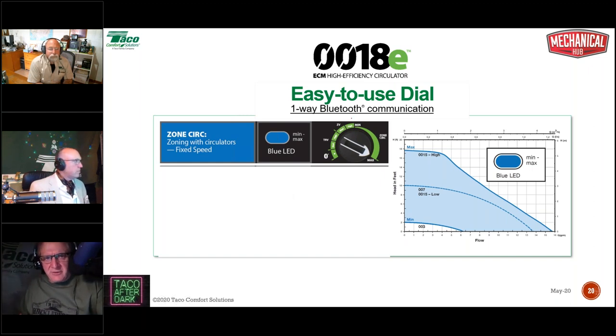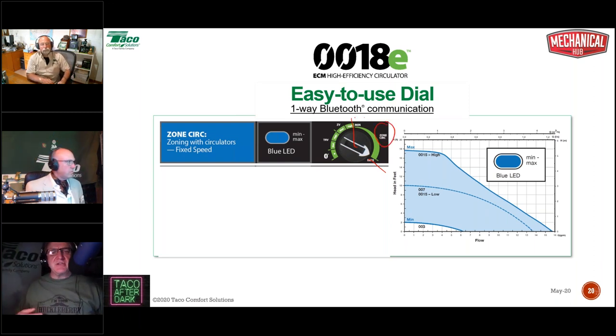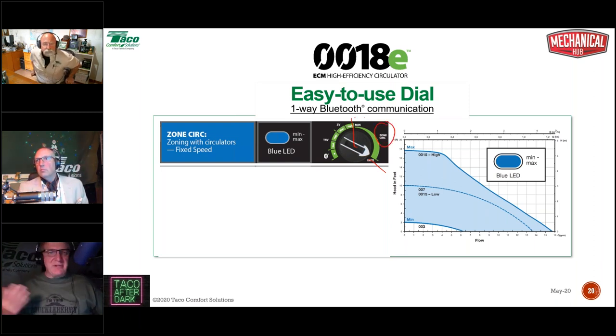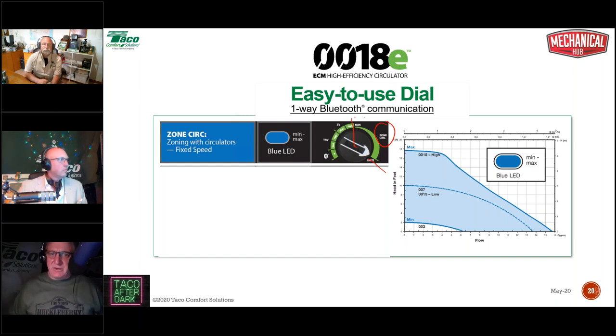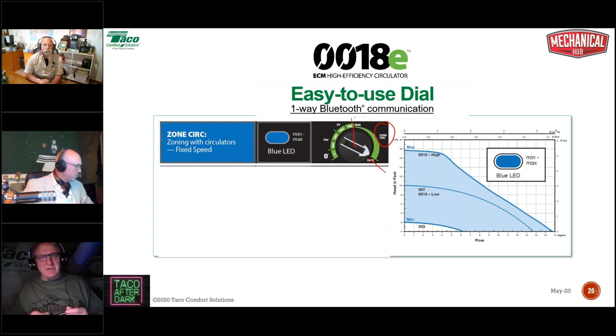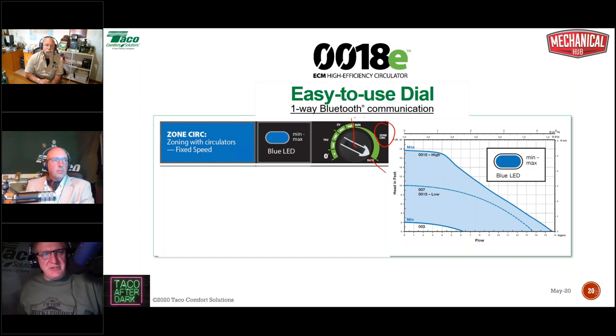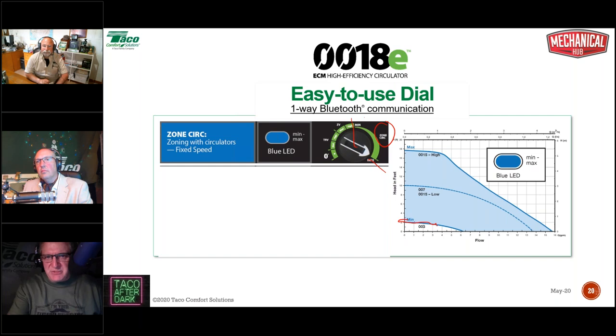Over here on the right hand side of the dial, it says zone circulator right there. Okay, it says zone circulator. If you're using this as a zone pump, we already know a delta P pump's not going to vary its speed when used as a zone pump. It's going to find its happy spot where the system curve intersects the performance curve, and that's what it's going to do, right? With the 0018E, we have the ability to set the fixed speed that we want. And in this case, we can make it whatever speed we want, anywhere from this minimum speed right here all the way up to the maximum speed up there.